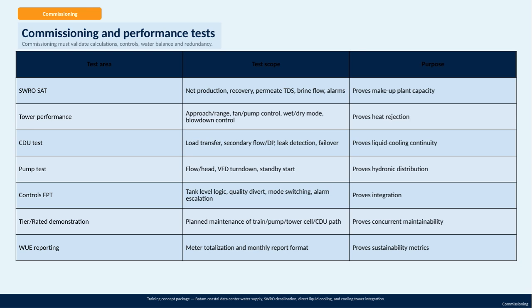First, the SWRO SAT test checks net production, recovery rates, permeate TDS levels, brine flow, and alarm functions to prove the makeup plant's capacity. Next, tower performance testing verifies heat rejection by assessing approach and range, fan and pump control, wet and dry modes, and blowdown control.